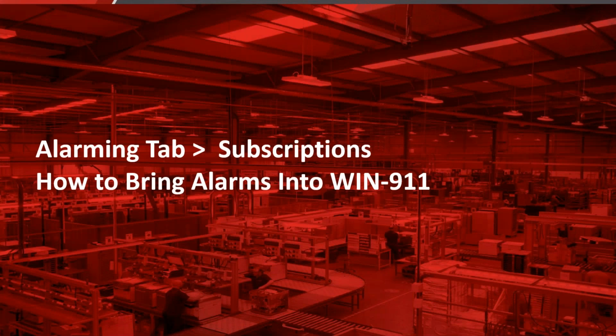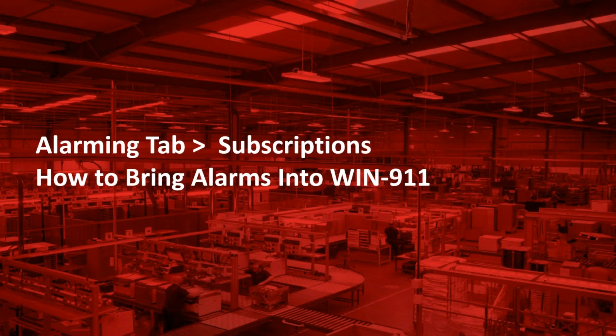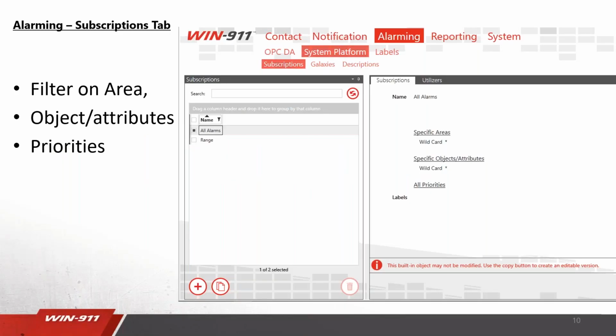All right, so how to bring in the alarms. You cannot do a direct import of tags. You have to actually use subscriptions, and subscriptions are like queries to say, give me a range of object names, or give me specific object names, or filter on certain object names or part of the name. You can also do it by priority. And here are our options.